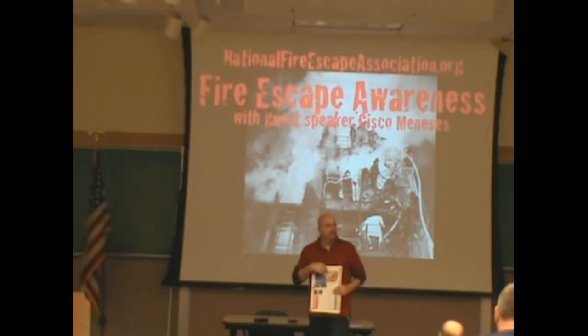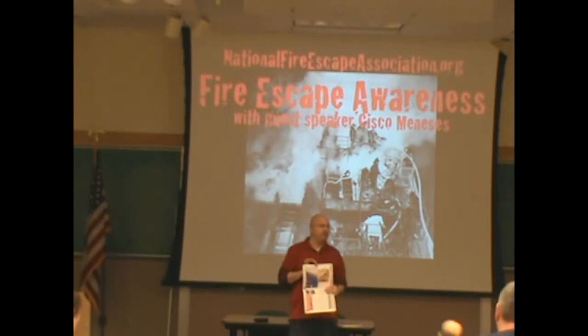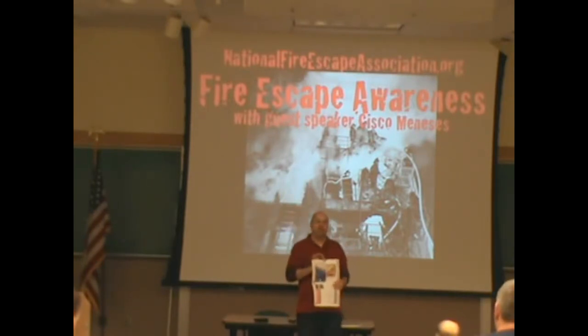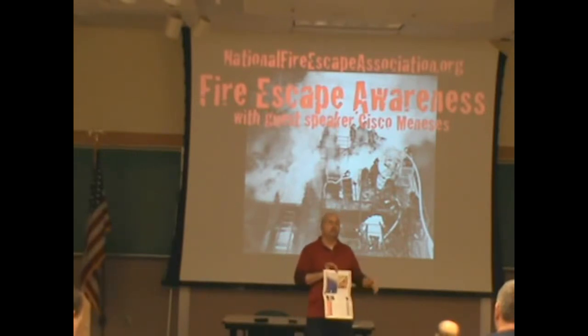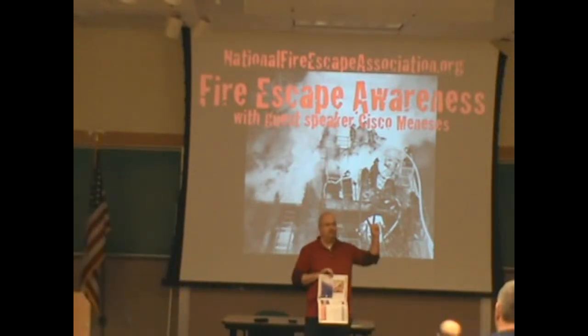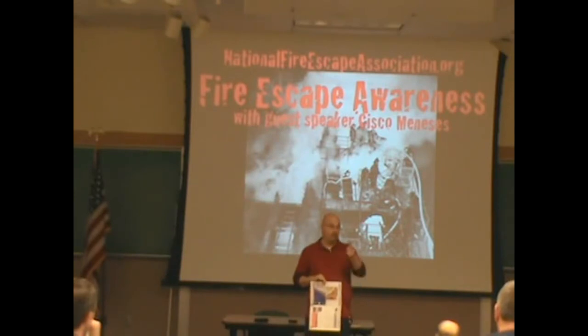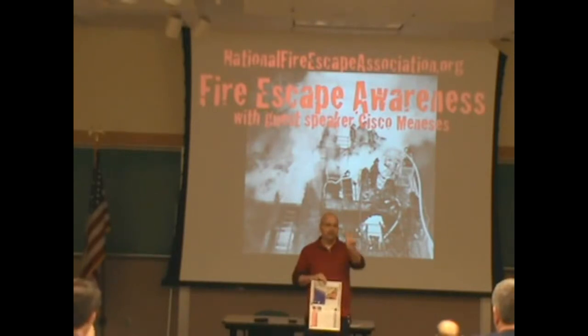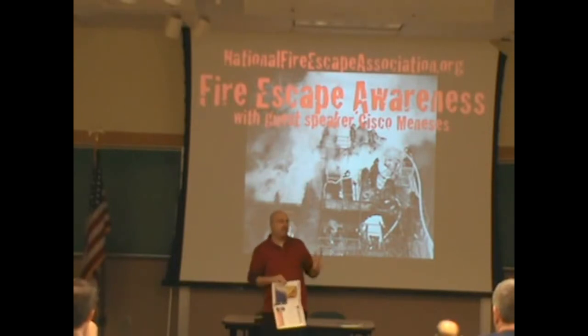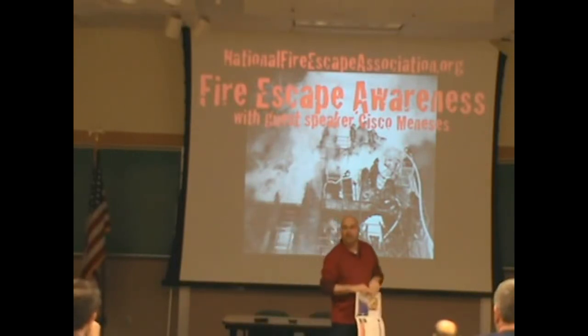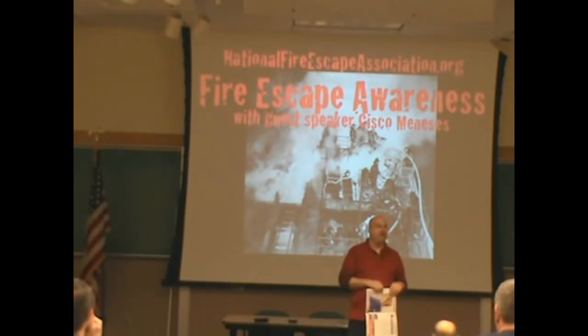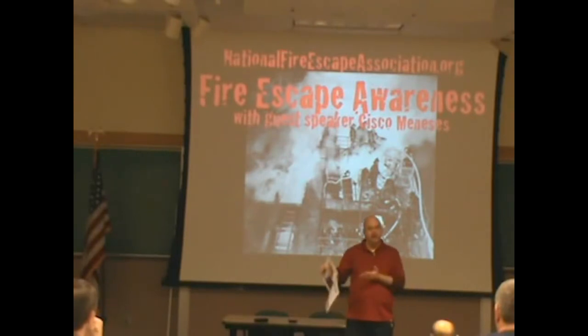Why are we going to mention OSHA? Today you're going to find an OSHA code — 1910.37 — that says any building under repair or alteration has to have two means of egress. Should it not have two means of egress, such as a front stair and a bad fire escape on the back, you can close that building. OSHA says an employee can't occupy any building that doesn't have two means of egress, or they've provided alternative means — meaning they can keep that fire escape and put up scaffolding overnight.